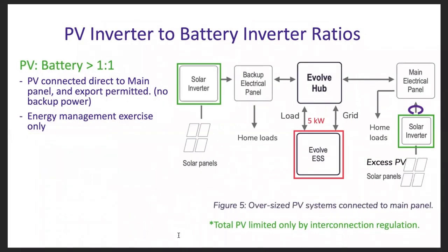And then in cases where the PV inverter to battery inverter ratio exceeds 1-to-1, say for example, you've got 10 kW worth of PV, you've got 2 5 kW string inverters, that PV needs to be split up, where one would be connected directly to the backup electrical loads panel, and the other would be connected in parallel to the battery system at the service panel. And this, of course, is in interconnection agreements where export to the grid is allowed. And this is an energy management exercise.